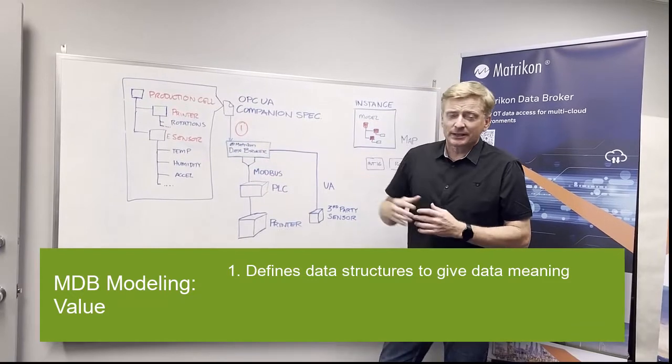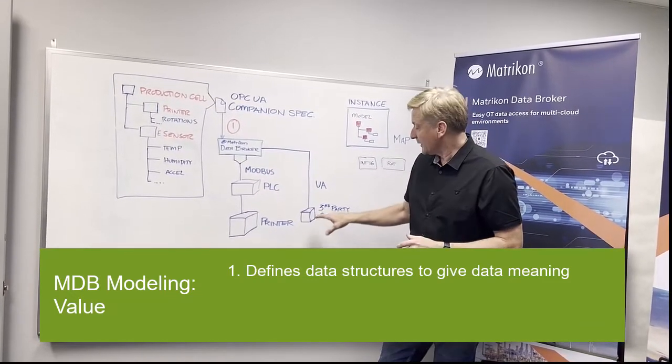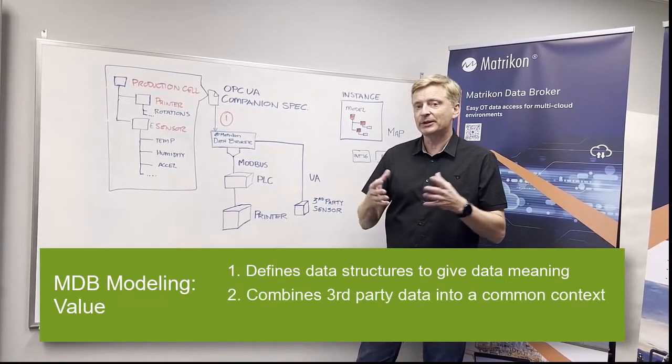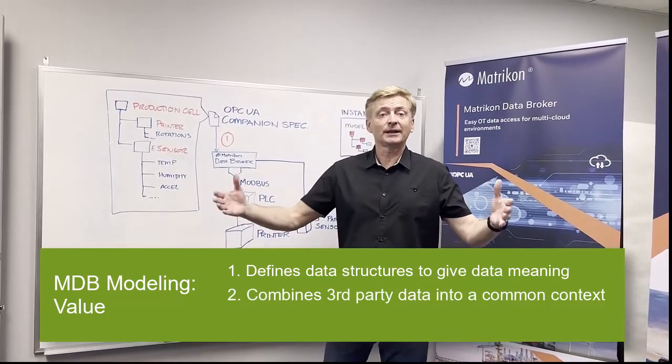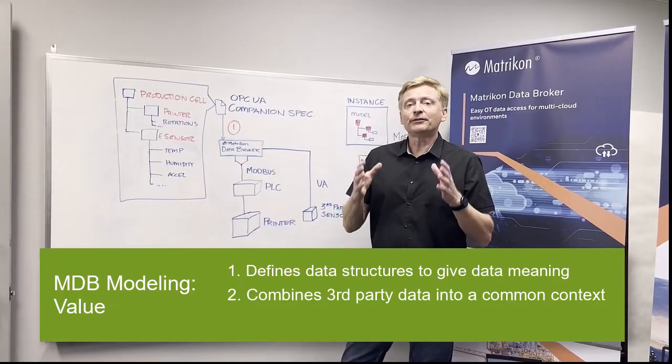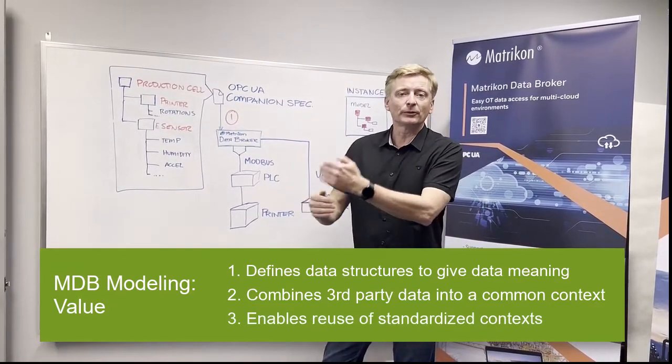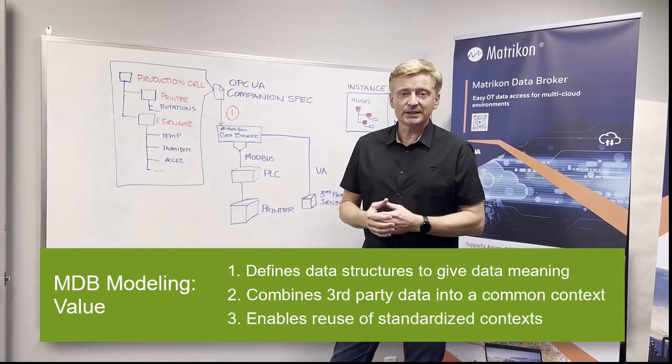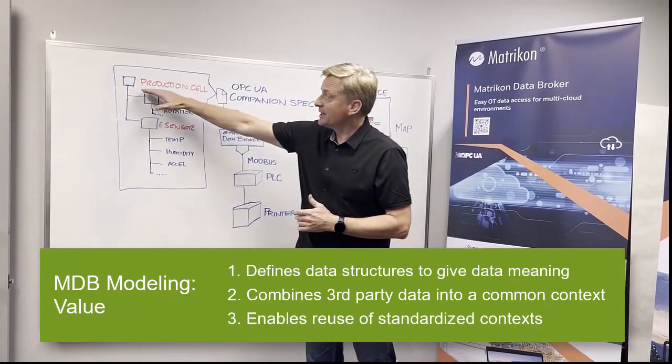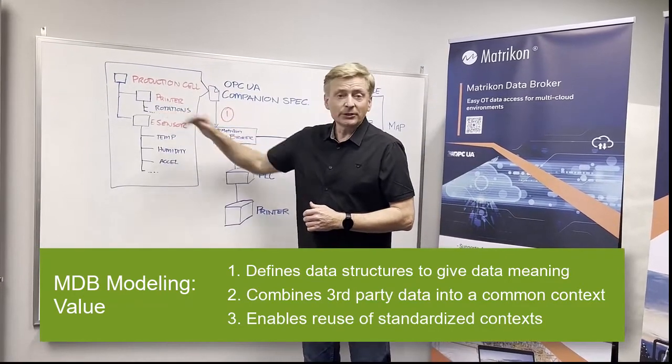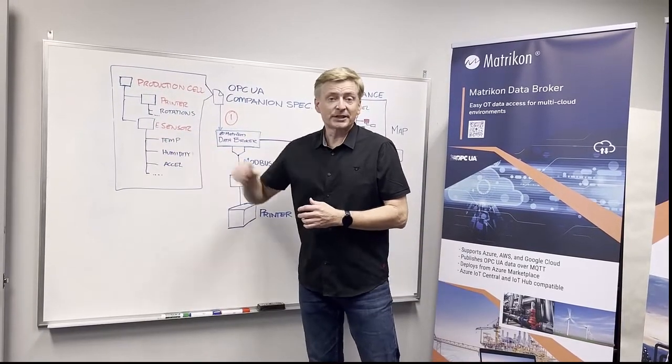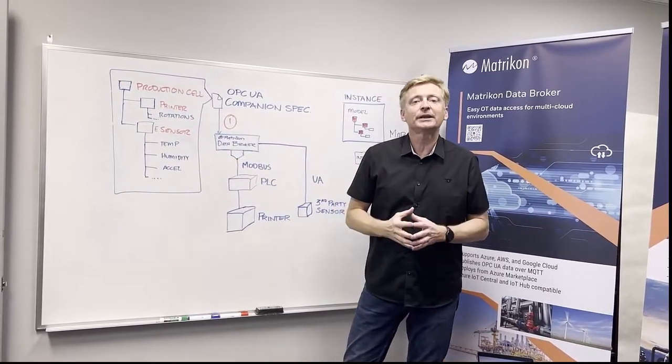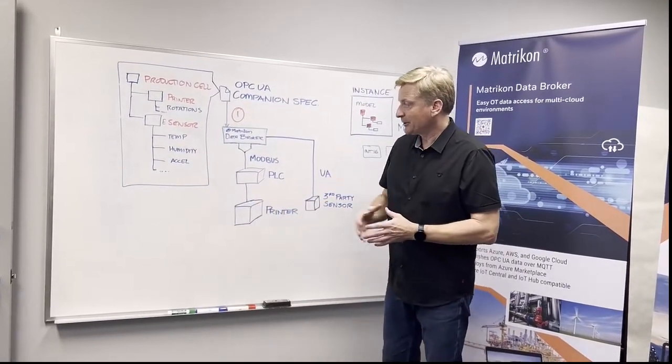Now the key thing is when you want to organize your information so that you can attribute whatever's coming from the sensor and tie it to the printer and maybe in your factory have it as the same as like for example the production cell or production line in that plant. What we're doing is using OPC UA companion specifications to define the model so they can be reused over and over whether it's a custom model done in the plant or you're using a recognized model that's basically standardized across an industry. So in this case we created a model, let's call it a production cell, and in that production cell we've got the printer information which is coming off of our printer, but also we'll have to tie in the environmental sensor, so we might have things like temperature, humidity, whatever you're getting off the sensor, maybe vibration to make sure that the bearings aren't wearing out within the printer.